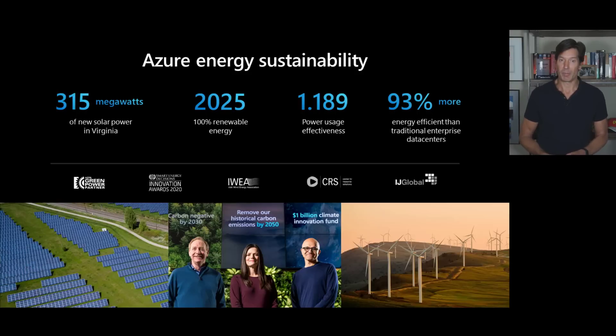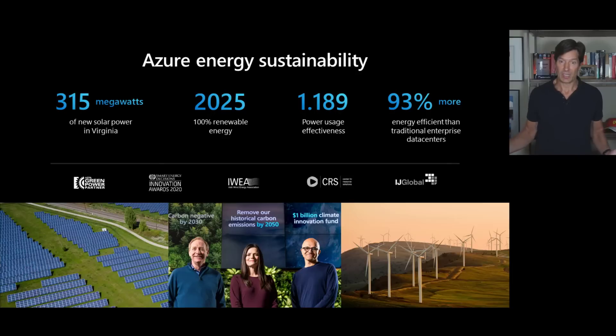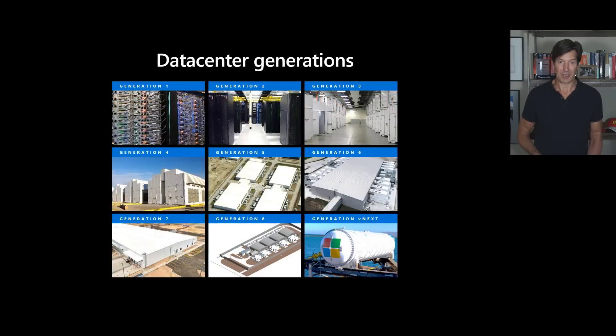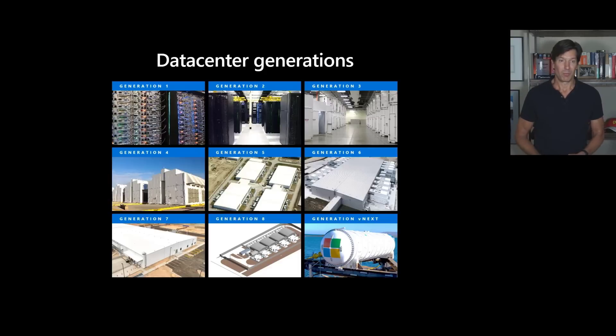Our average PUE — power usage effectiveness — which is the industry standard way to measure data center efficiency, is just 1.189 across all of our data centers, including data centers we created that are still operating at 15 years old. Our latest generation data centers have even lower PUEs. To illustrate this, I want to walk through Microsoft's data center evolution, going back in time to see how we've taken advantage of newer technologies and experimented with new ways to be efficient.